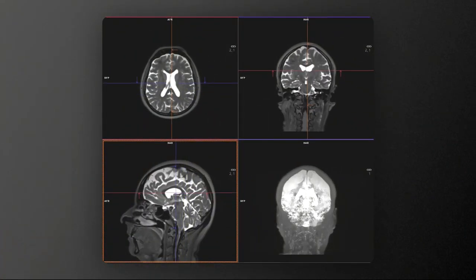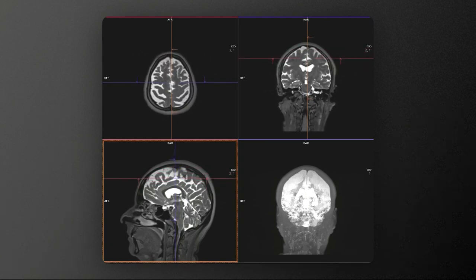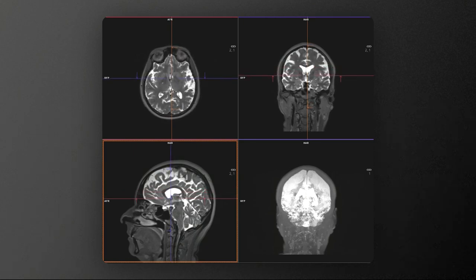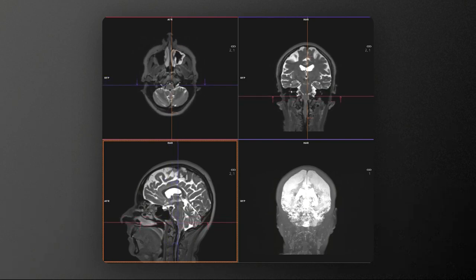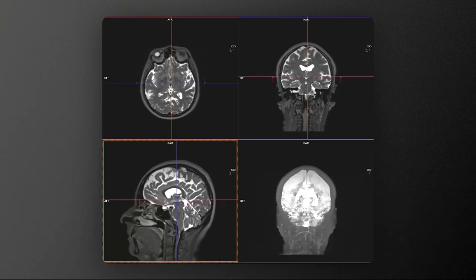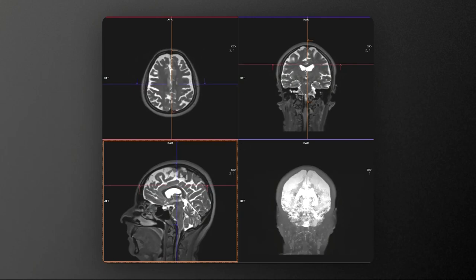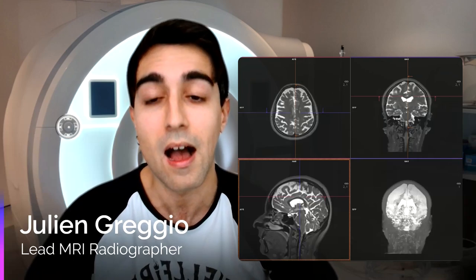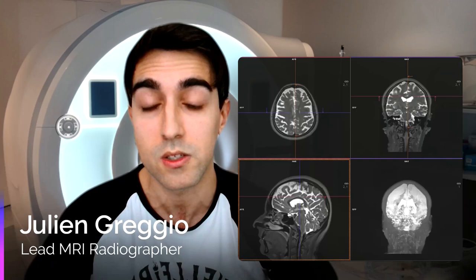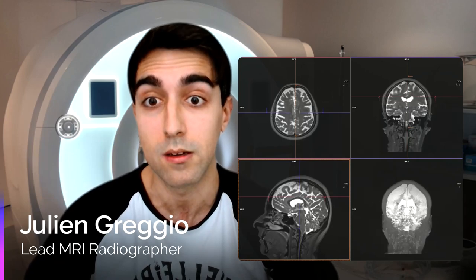So, as far as I am concerned, in this specific case, despite some minor differences with the overall quality perceived, I would say that the resolution we can have on these MPRs generated from the 1.5 mm slice thickness native acquisition is almost comparable to the one just seen before. Bear in mind though that the radiologists might have a different opinion, so if you rely on MPRs to replace other 2D sequences, you need to make sure you have a high level of detail, so very good quality MPRs. The closer you get to an isotropic condition, the better the results will be.